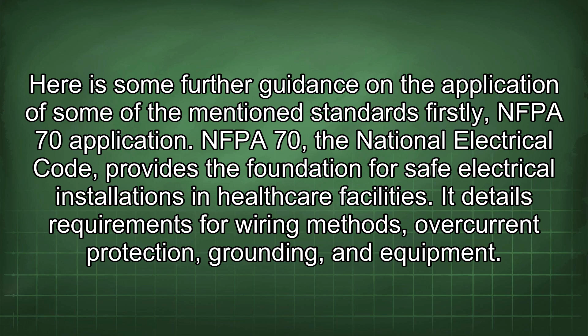Here is some further guidance on the application of some of the mentioned standards. Firstly, NFPA 70 application. NFPA 70, the National Electrical Code, provides the foundation for safe electrical installations in healthcare facilities. It details requirements for wiring methods, overcurrent protection, grounding, and equipment. When applying NFPA 70, pay close attention to Article 517, which provides specific requirements for healthcare occupancies. This article addresses essential electrical systems, isolated power systems, and other unique aspects of healthcare electrical installations.